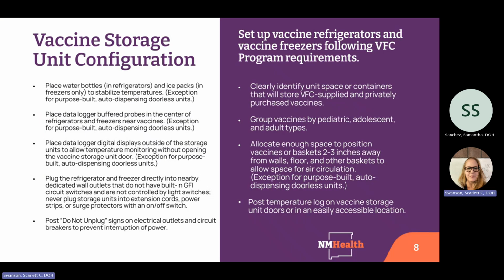For your vaccine storage unit configuration, place water bottles in your refrigerators and ice packs in the freezer or frozen water bottles to stabilize temperatures. There is an exception for purpose-built auto-dispensing doorless units, or the Pyxis machines, and also pharmaceutical refrigerators and freezers. If the manufacturer does not recommend using water bottles or frozen ice packs, there's no need to use them. Place your data logger buffered probes in the center of refrigerators and freezers near the vaccines. Place your data logger's digital displays outside of the storage units to allow temperature monitoring without opening the vaccine storage unit door.